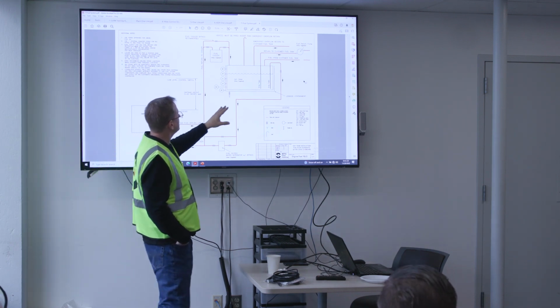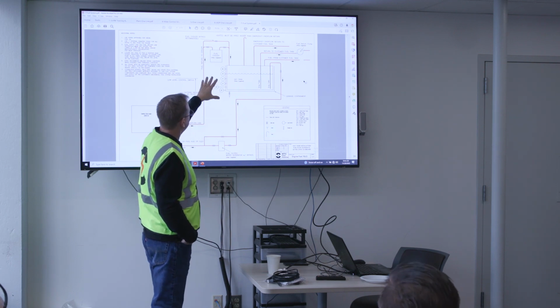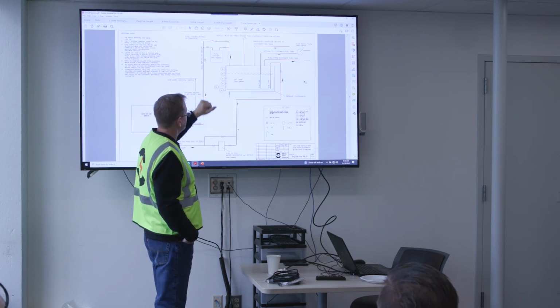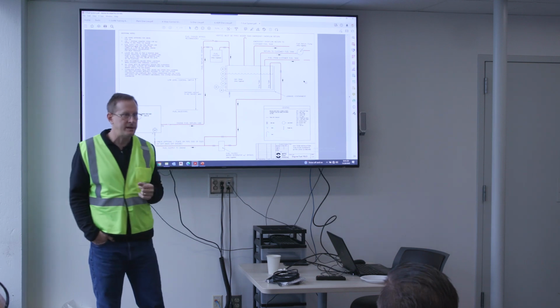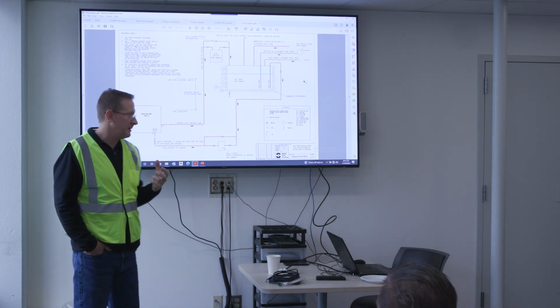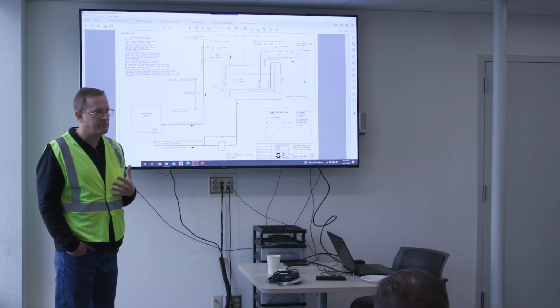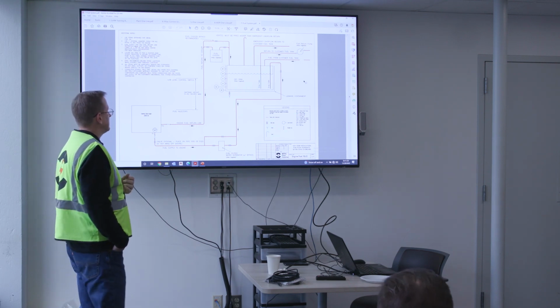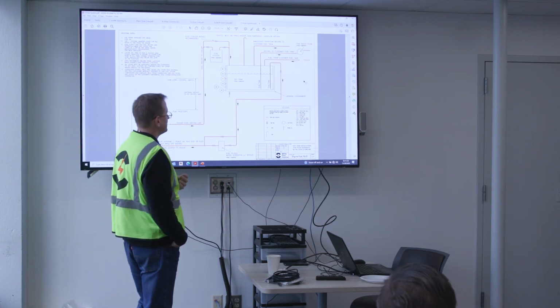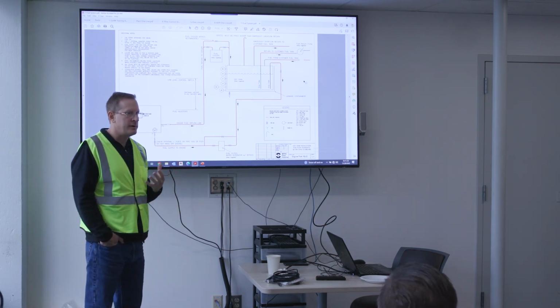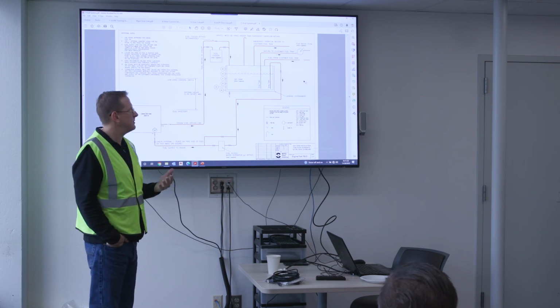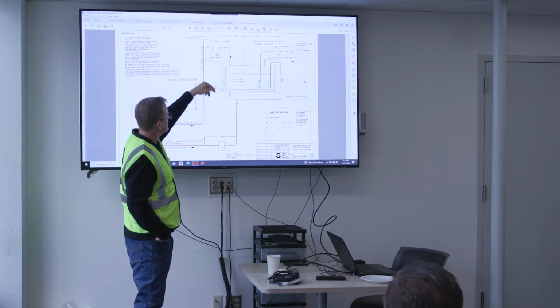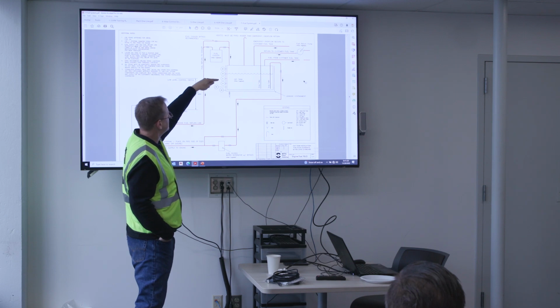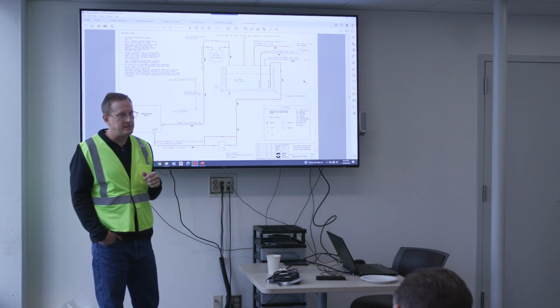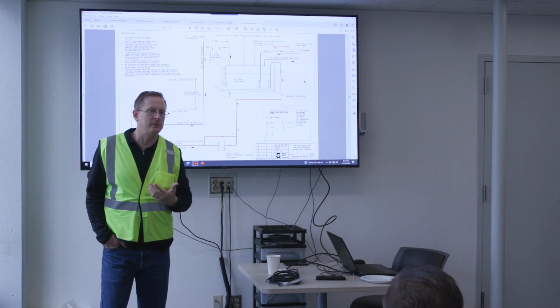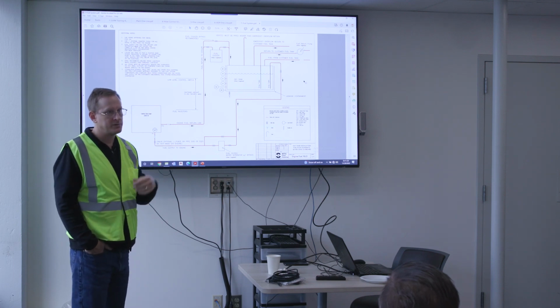The day tank has a number of floats within it that control the filling of the day tank. The day tank comes with a fuel control panel that is its own self-contained way of controlling the fill of the day tank itself. So via various floats, via a high control float and a low control float, the tank itself will call for fuel from your bulk storage.